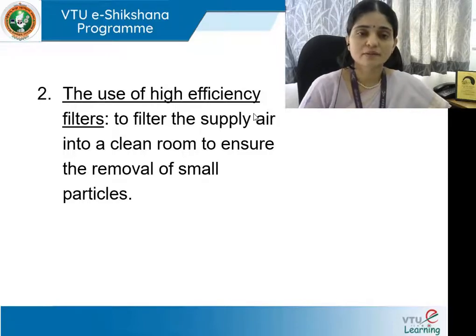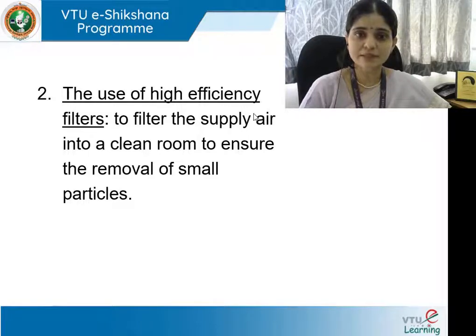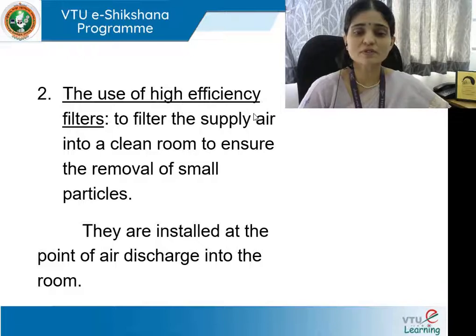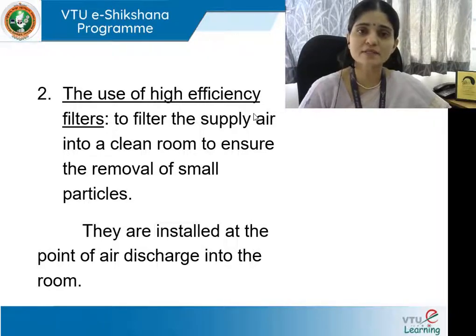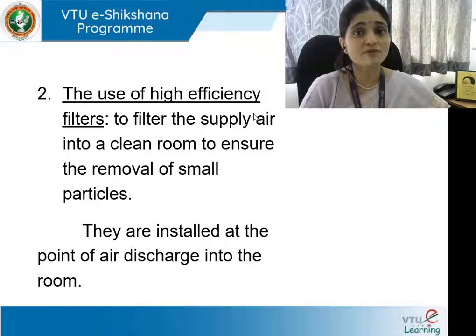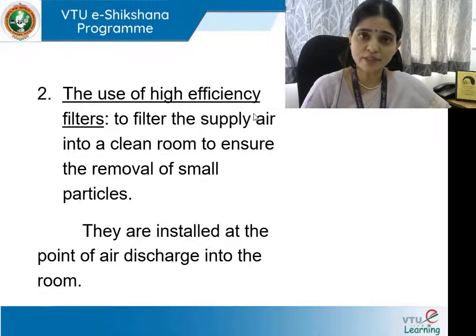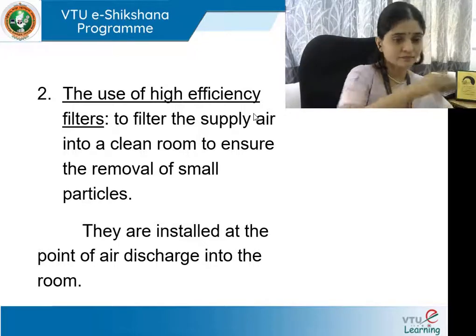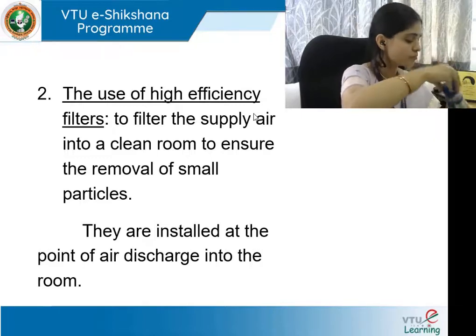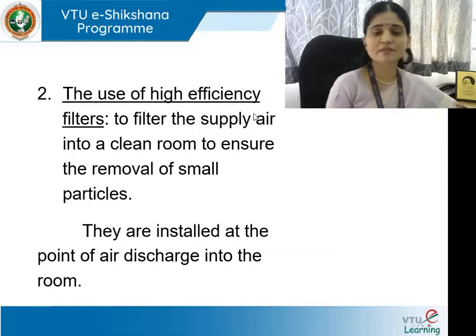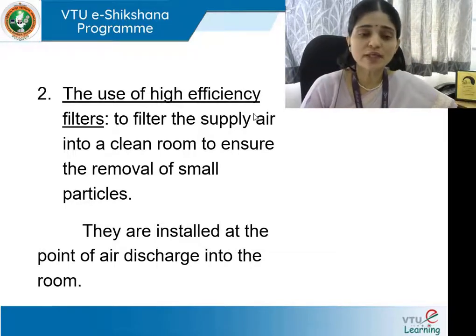Second: the use of high-efficiency filters to filter the supply air into a clean room, ensuring removal of small particles. These are installed at the point of air discharge into the room. Normally, filters are located at the return air grille before air reaches the evaporator or cooling coil. In a clean room, in addition to filters at the return air end, there are also filters at the supply end — the point of air discharge.